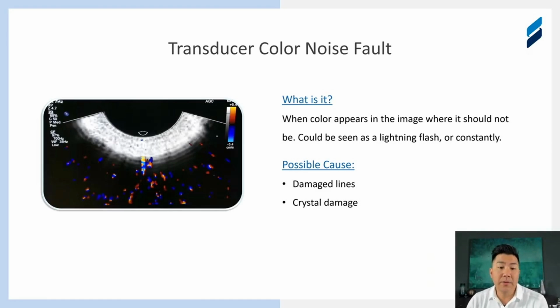Here's an example of color noise in a transducer. We've identified that it is the transducer. Here's what you may see. This could be just color. This is an air scan, as you can see. Color is just kind of flashing through, and in particular, you see color here that it's pretty clear is not even with the rest of the color image, that this is actually induced noise and information that's being transmitted and received that isn't there in the actual scan itself.